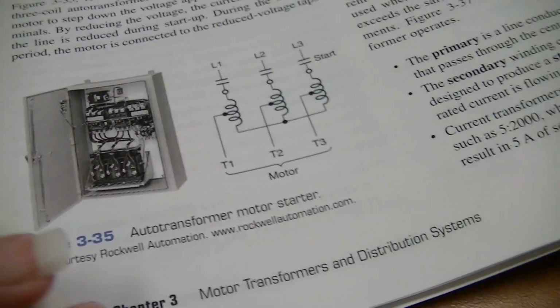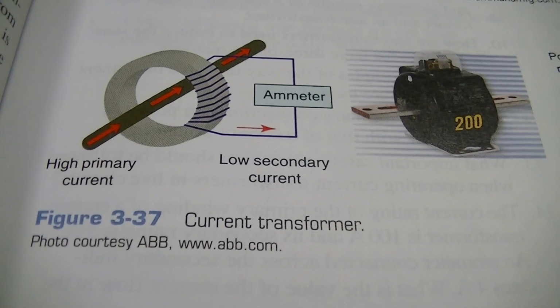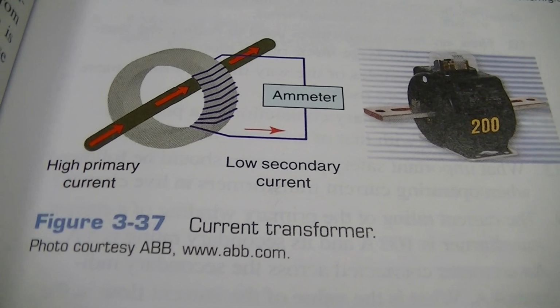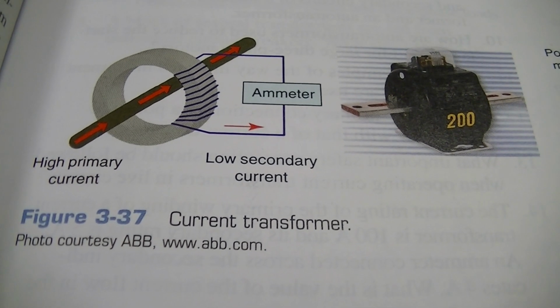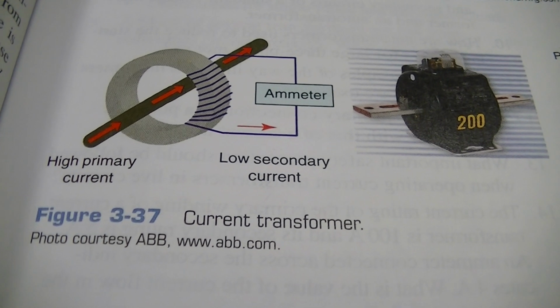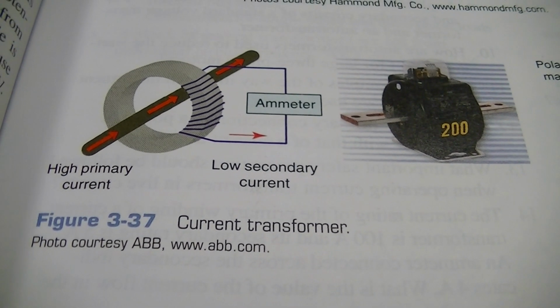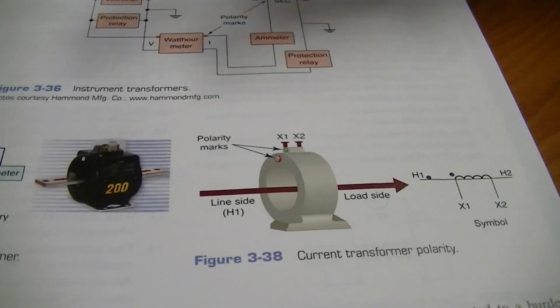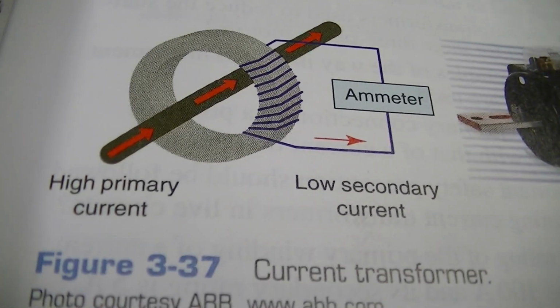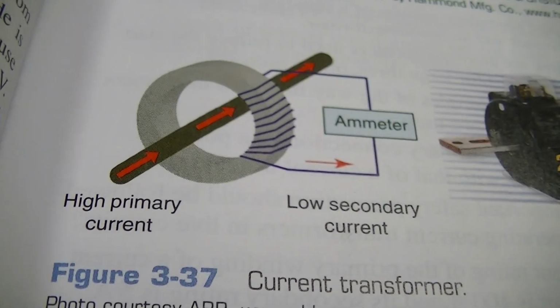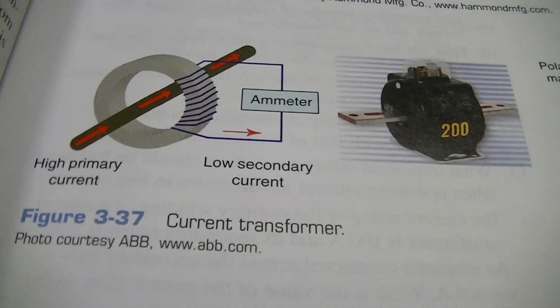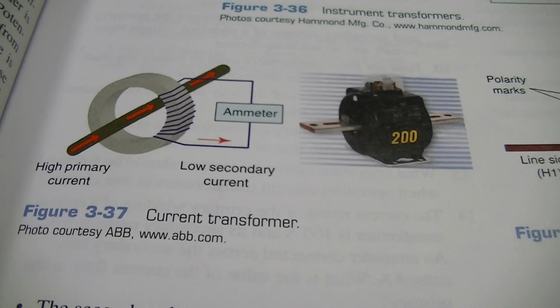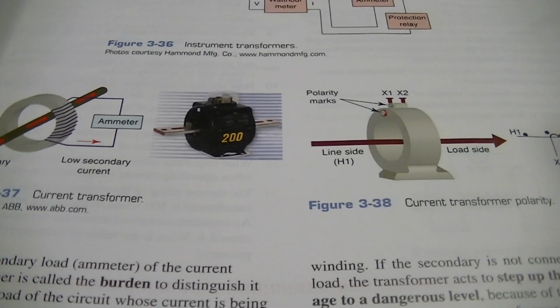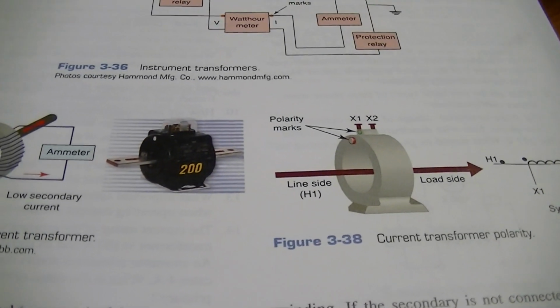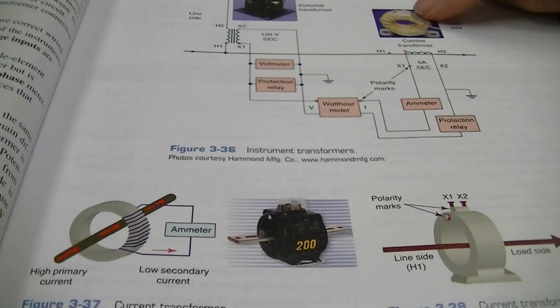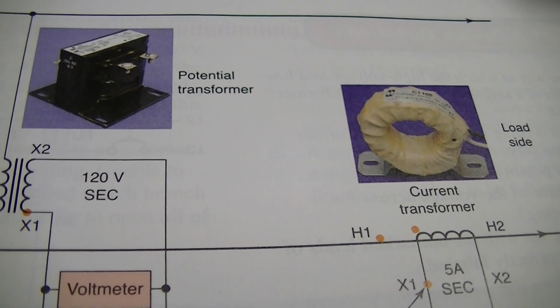Along down here, we have a current transformer. Very common way of feeding, for example, an ammeter. Let's suppose I have a motor that's got 200 volts, I'm sorry, 200 amps. Well, you probably don't want to put 200 amps into a little tiny ammeter, okay? Or else you're going to have a great big ammeter to be able to handle the 200 amps of power that it's going into. So what they do is they take an ammeter and then they have a single conductor that's got the primary current in it. They take a number of wraps, and the number of wraps of it will give you a ratio, and that ratio is used to reduce the range of a gauge by whatever that ratio is, 1 to 10, 1 to 100, whatever. So there's lots of different shapes. They're almost always round, helical sometimes.